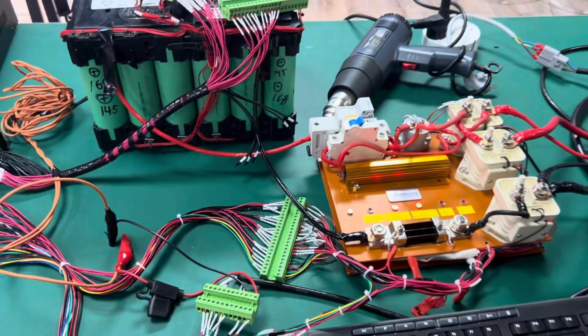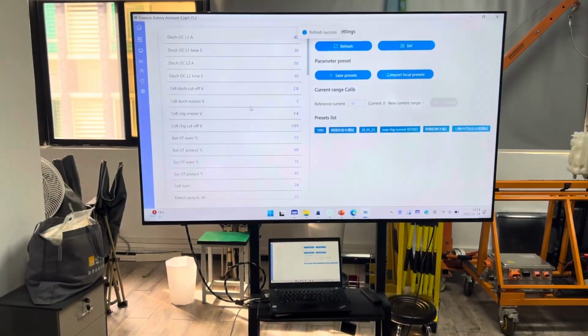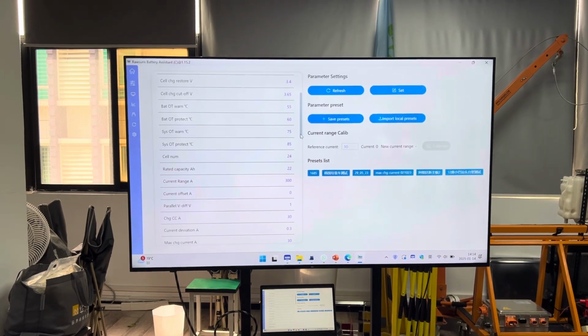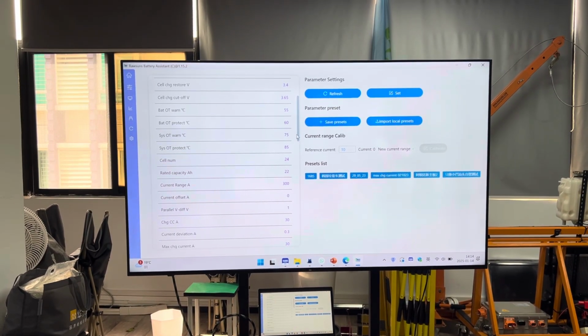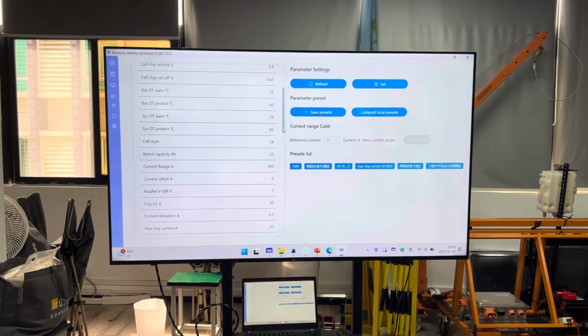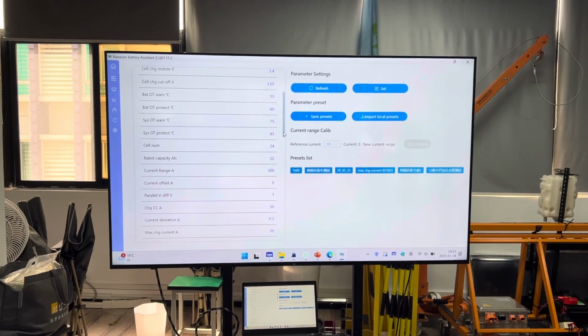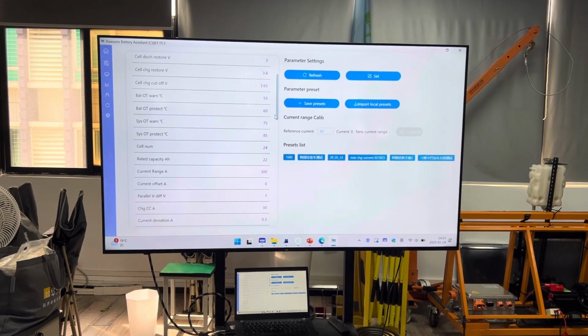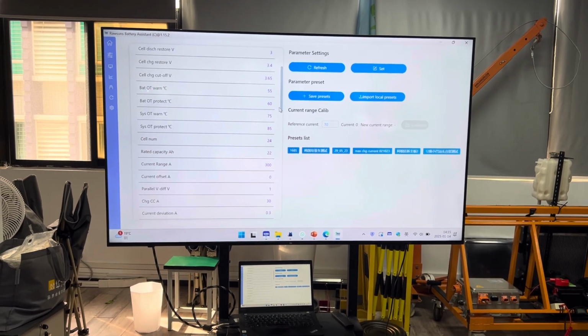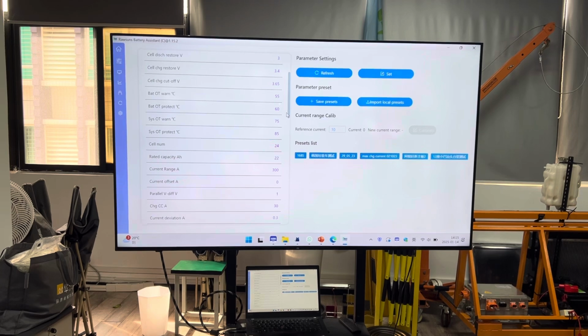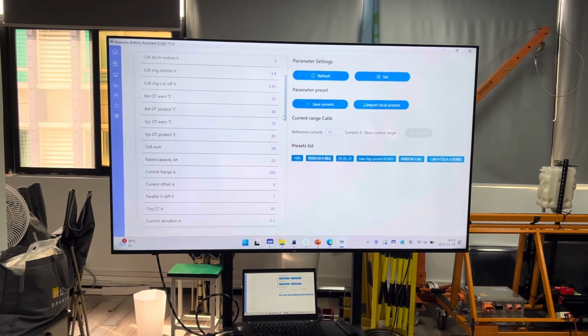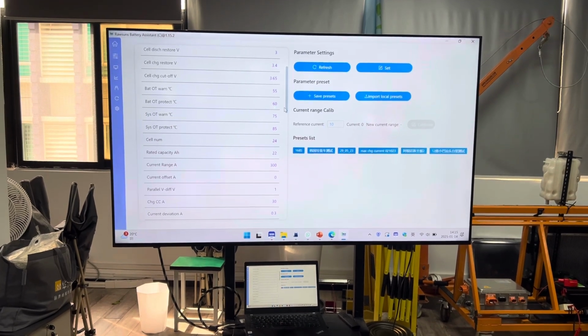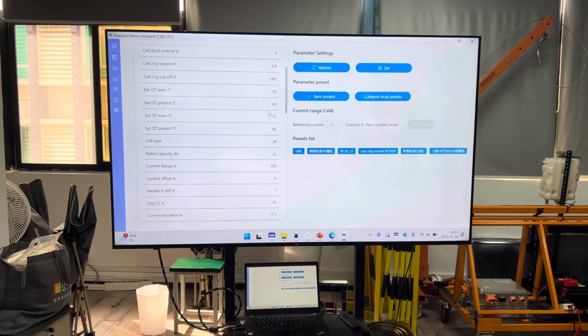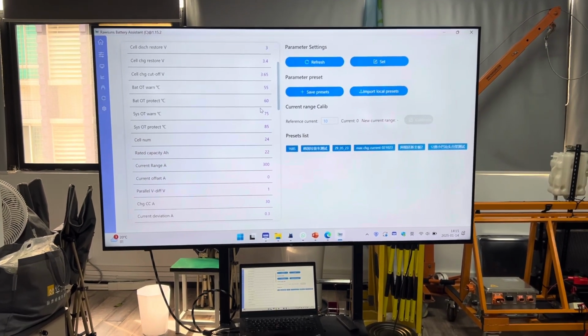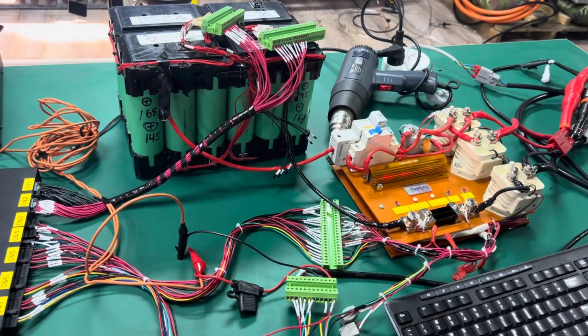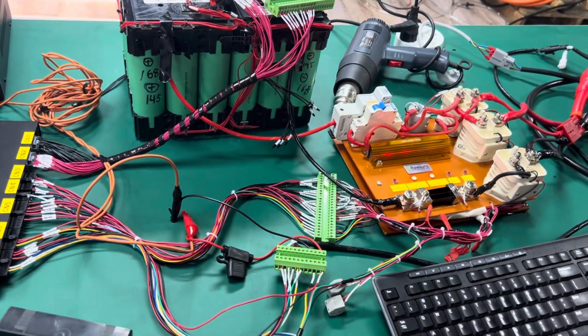How can we set the cooling temperature? We can set the cooling temperature in the settings. We can see down here: battery overheat warm temperature is 55. Battery overheat protect is 60 centigrade. It means that when the temperature goes to 60, the cooling will start to work to turn on the cooling relay, so the cooling system will start to work.